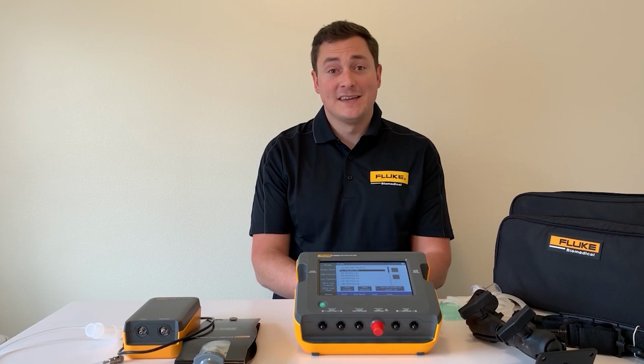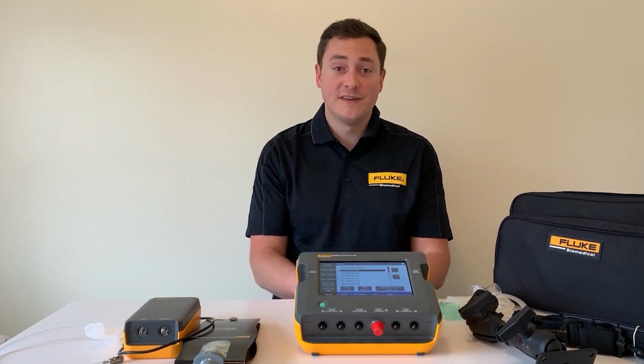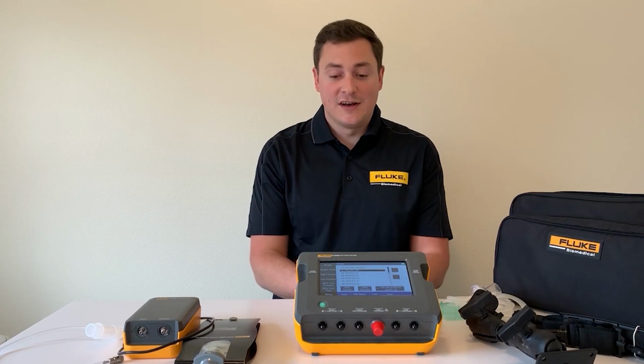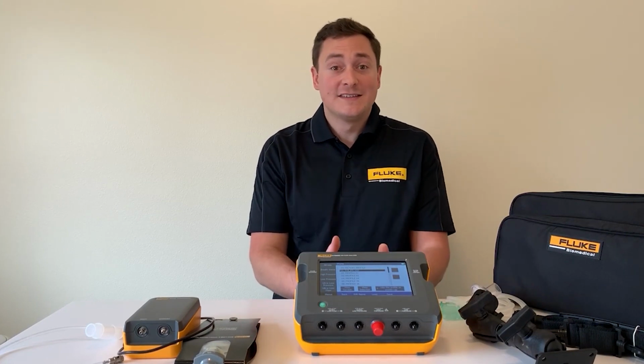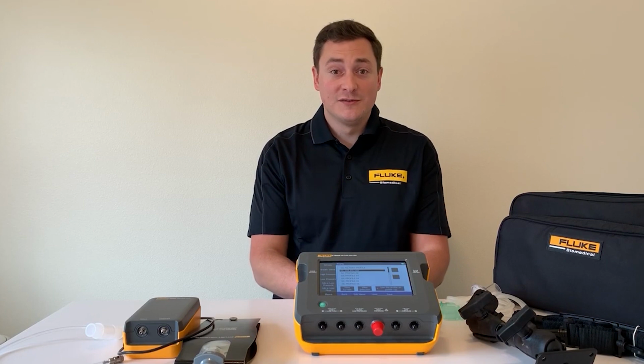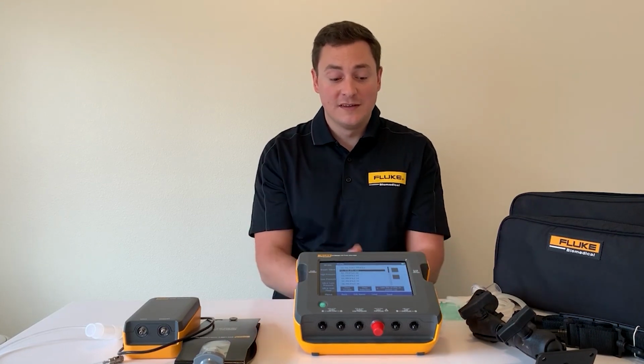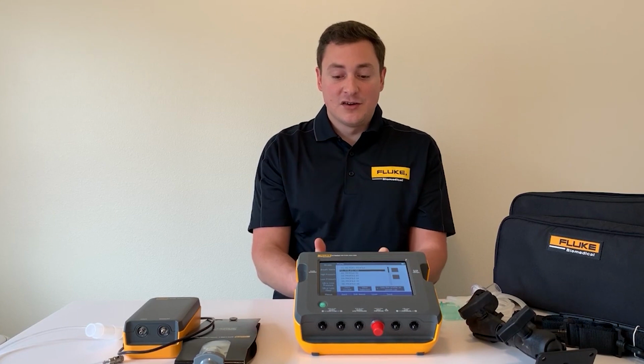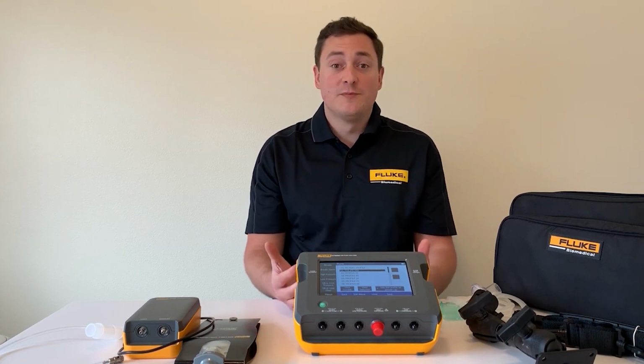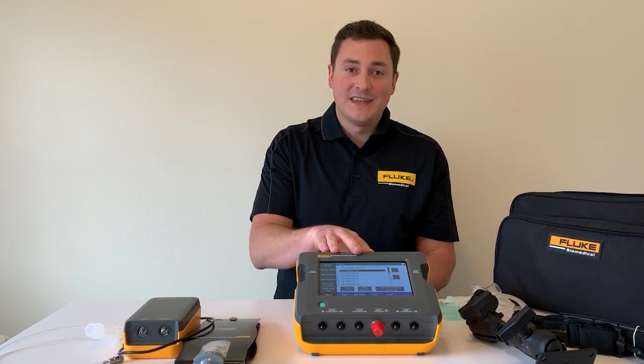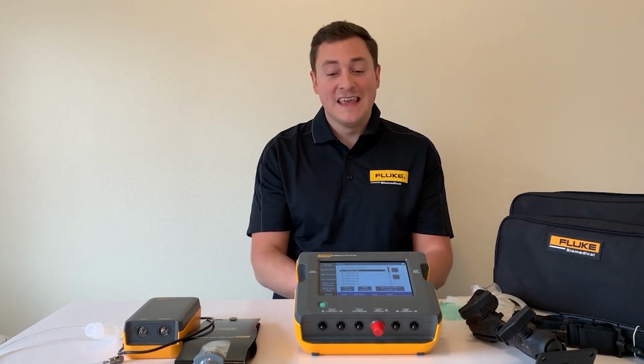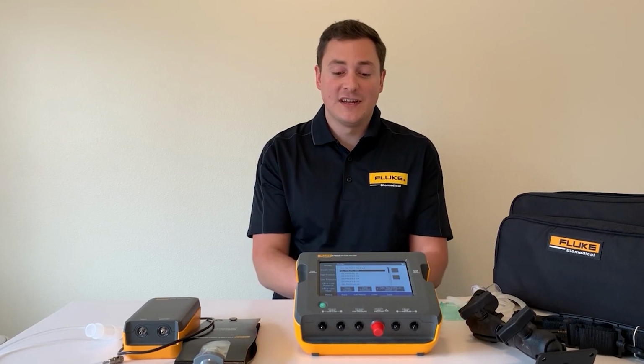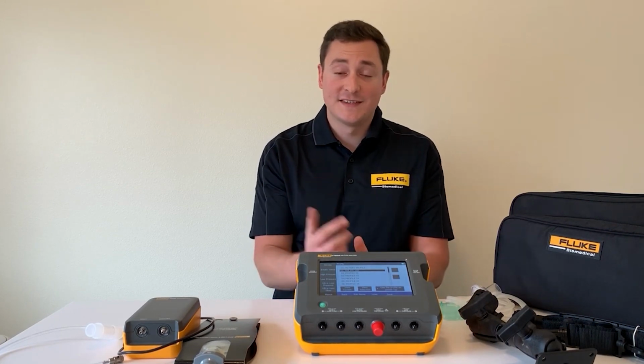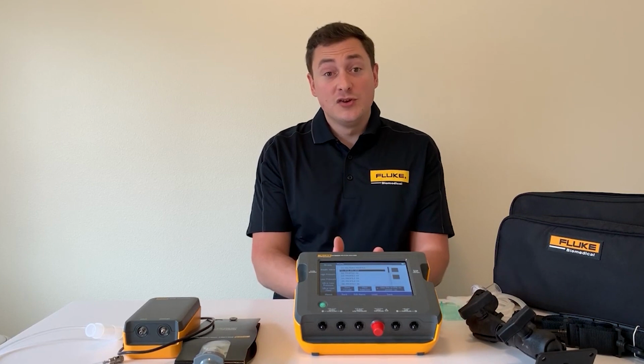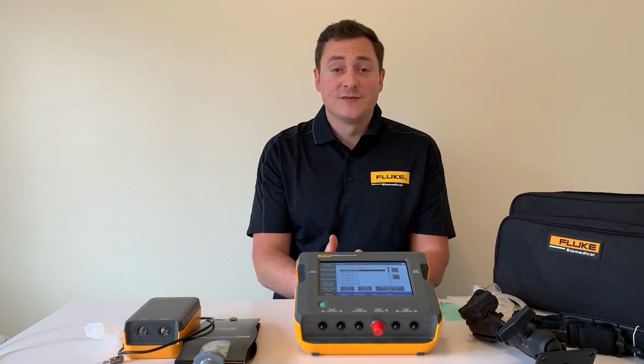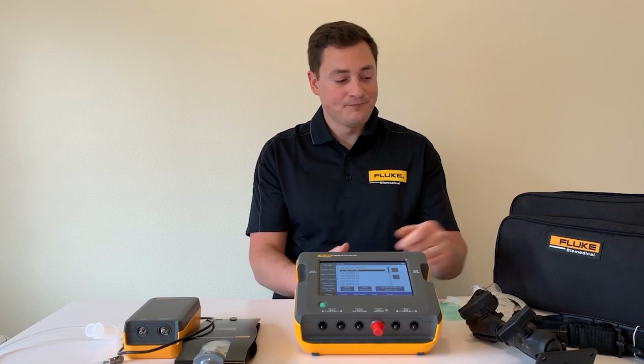Portability, right? Size and weight have been dramatically reduced. If you know our VT Plus, this is much smaller. And we've thought about where you have to do your work. An anesthesia table is not large, so you need to have a smaller footprint, and we've really helped that along. In terms of your workspace, you're going to bump your product, right? So if it gets bumped, it's not going to move. We have rubberized feet on that. If it falls off, this is a ruggedized unit. We have drop tested it from 1 meter on all 6 sides. It will take a beating, but you do want to make sure that your unit's calibrated afterwards because we're dealing with patient safety at the end of the day.